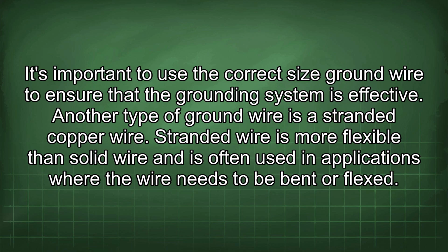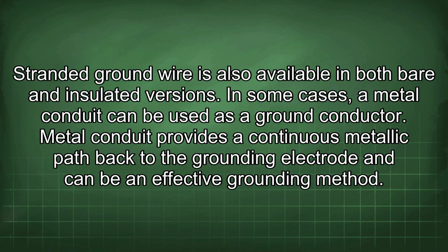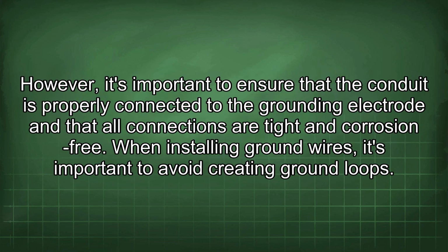Another type of ground wire is a stranded copper wire. Stranded wire is more flexible than solid wire and is often used in applications where the wire needs to be bent or flexed. Stranded ground wire is also available in both bare and insulated versions. In some cases, a metal conduit can be used as a ground conductor. Metal conduit provides a continuous metallic path back to the grounding electrode and can be an effective grounding method. However, it's important to ensure that the conduit is properly connected to the grounding electrode and that all connections are tight and corrosion-free.